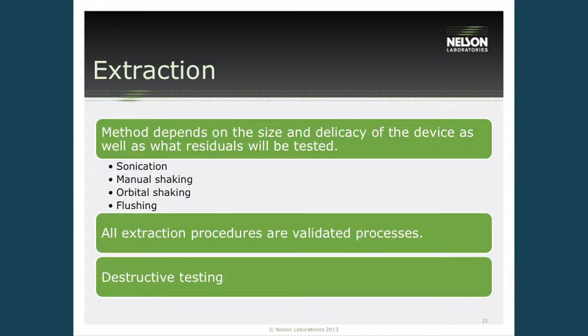We need to make sure that all lumens and all cracks and crevices, all areas that have screws and so on are also flushed thoroughly to make sure that we're getting everything off the device that we possibly can. All these processes need to be validated to make sure that that process is best for that type of device. And then also it's important to perform this on devices that we can disassemble, or if we can't disassemble the devices, if there is some way that we can cut them up and flush every crack and crevice, which is a little difficult with the expense of a lot of medical devices, but it is the best scenario for that.